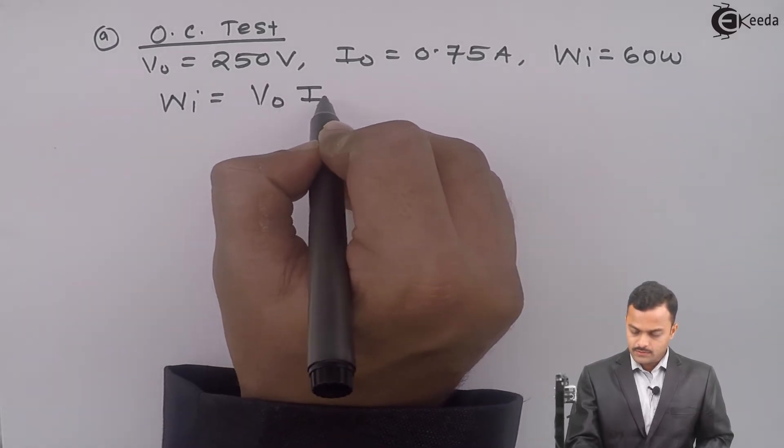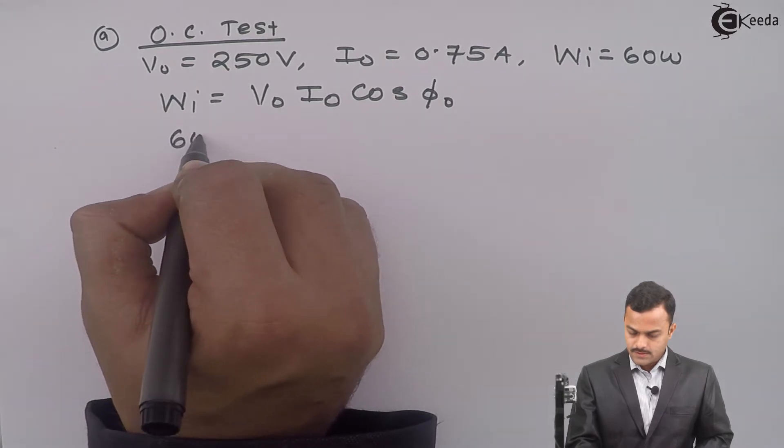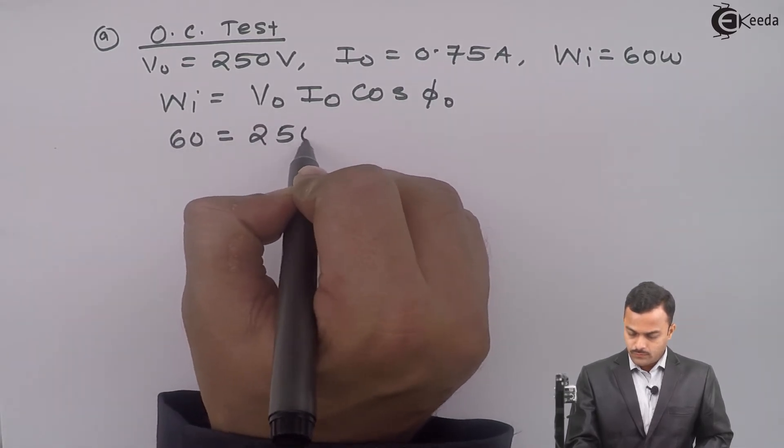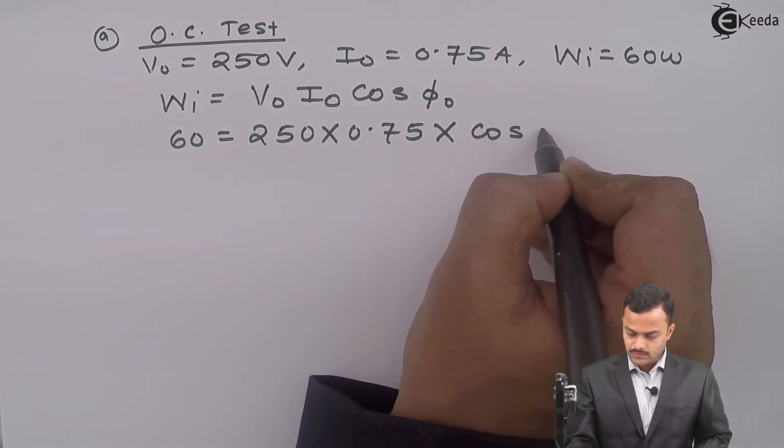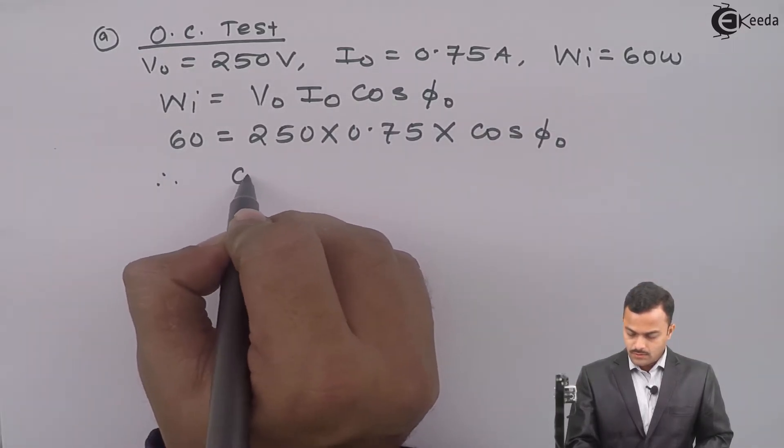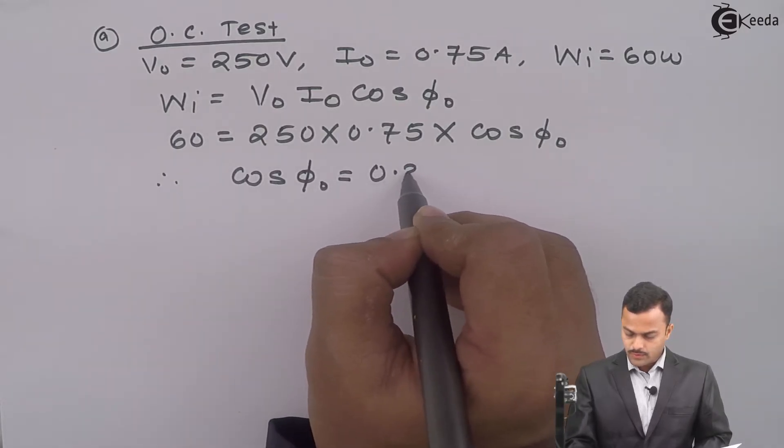W equals V0 I0 cos φ0. 60 equals 250 into 0.75 multiplied by cos φ0. If you solve, you will get cos φ0 equal to 0.32.